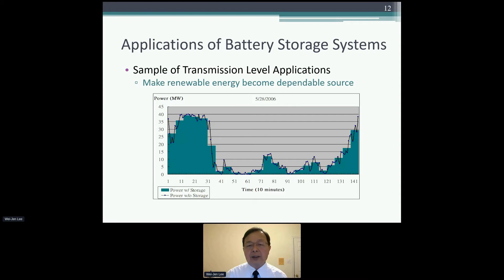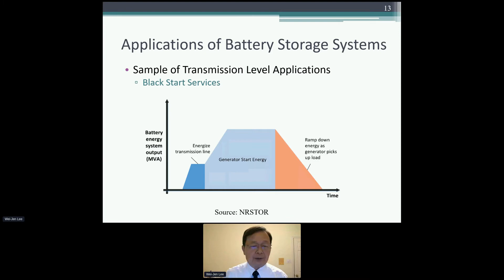This is basically what I mentioned about the black start service. If you look at the procedure, during the blackout you energize the transmission line and then probably pick up some of the load, because if you just energize the transmission line, you may end up with an over voltage issue due to line charging. So you plan ahead and pick up some critical load and maintain the system voltage. Then you can provide energy for the generator to start up, and ramp down the energy storage once they accomplish the goal of starting the first generation unit. So this can serve as a black start service.